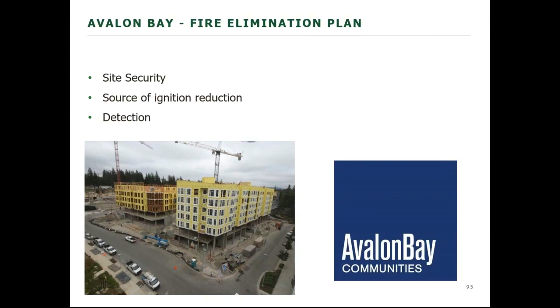And they also have early detection. And part of that, this is above what the code requires. They have Wi-Fi enabled remote sensors. And because they're Wi-Fi and they work off of batteries, you don't have to run a lot of wires. Some of them are hardwired, but they can be used from job to job to job. They collect many channels of data, including heat rate of rise, smoke, that kind of thing. And because they're Wi-Fi enabled, that information can be sent to any electronic device. It could be the job site manager, it could be 911, but it would help with early detection, but that is above what the code requires.